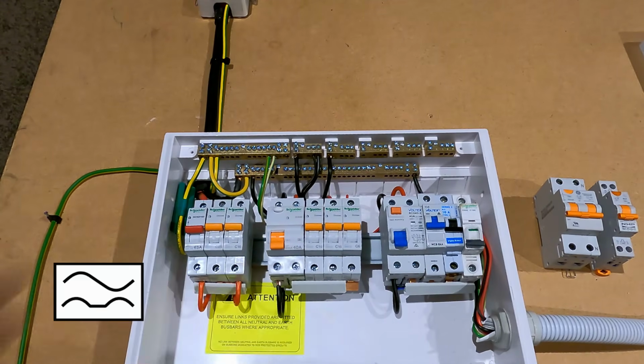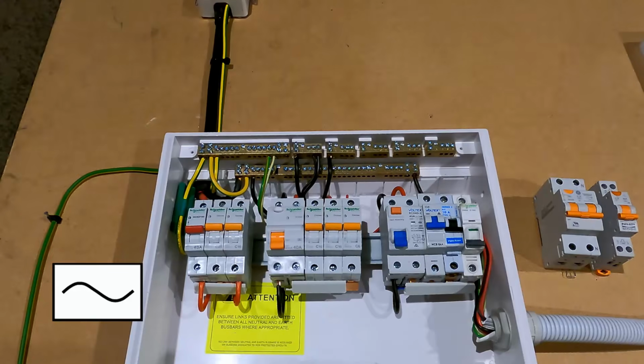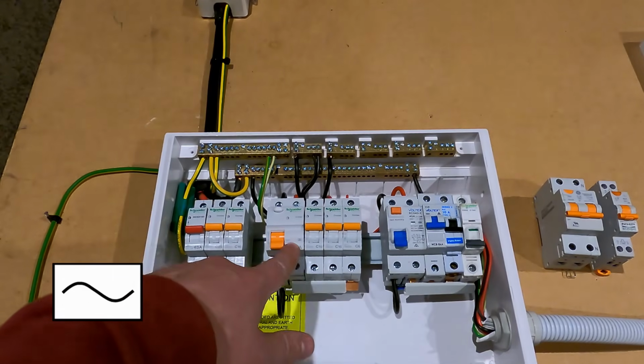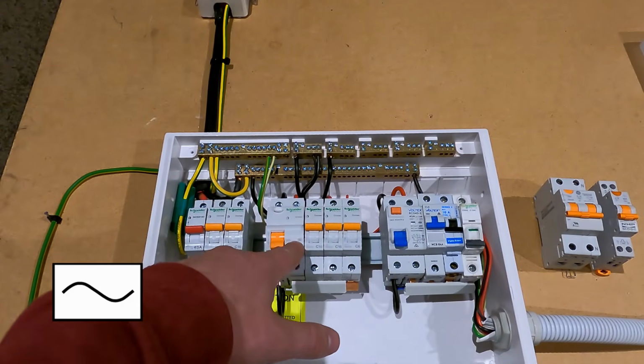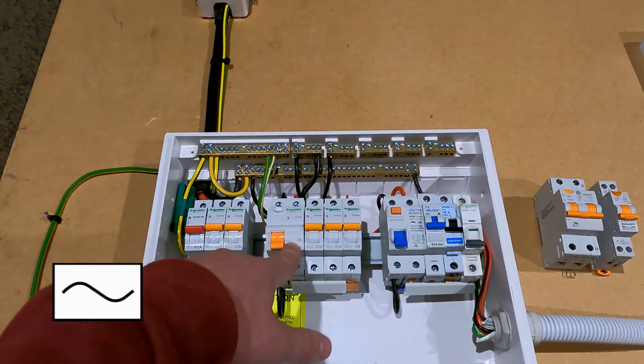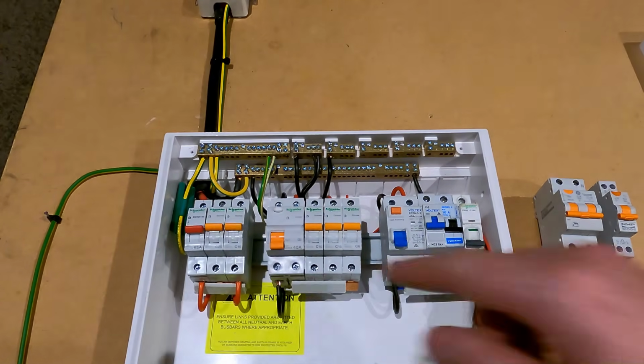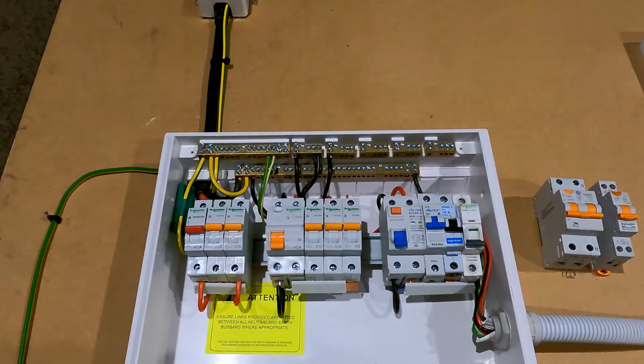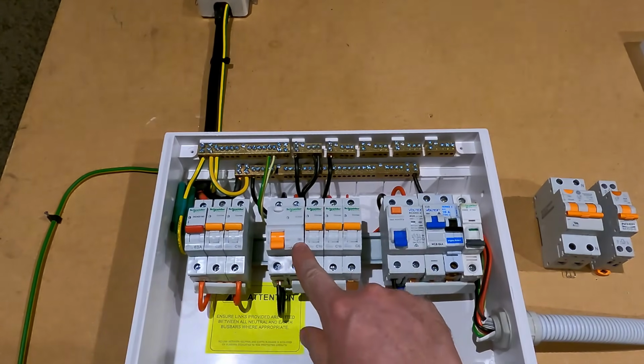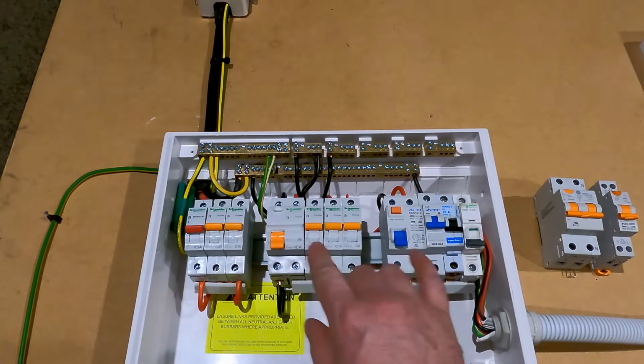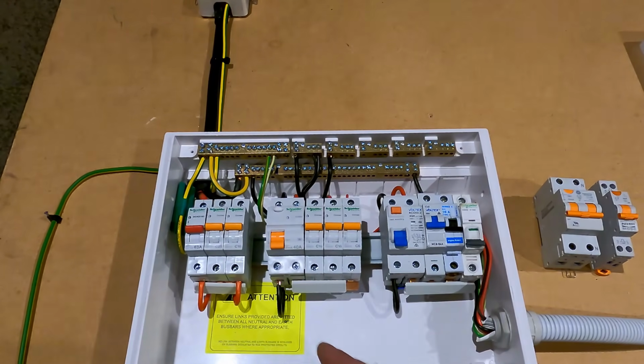Now in New Zealand, these are required. In Australia, you can have type AC RCDs, which just have the sinusoidal waveform in the box. So the type AC RCDs are suitable for most appliances anyway. Yeah, in New Zealand, with the pulsating DC, that protects the RCD from loads that have rectifier diodes or thyristors that have stuffed out and caused an issue.